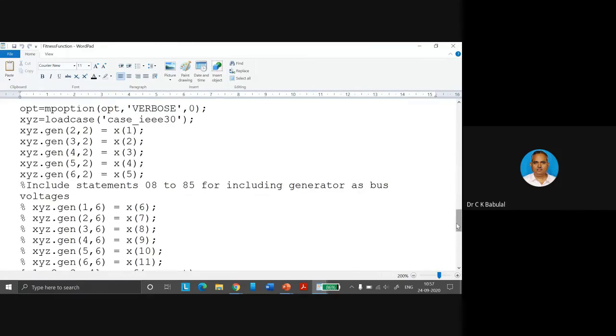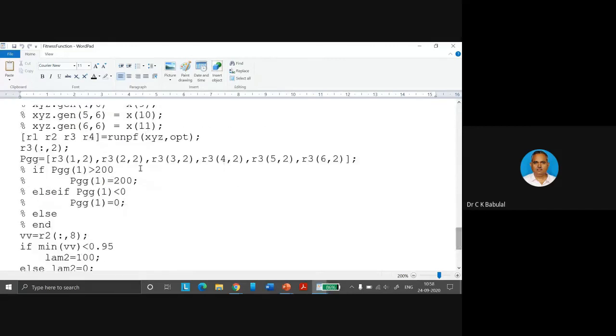Run PF is used to get the power flow, and the solutions are stored in results R1, R2, R3, R4. R3 will have the generator power output for all 6 generators, including the slack, and you can verify whether it's within the limit or not.